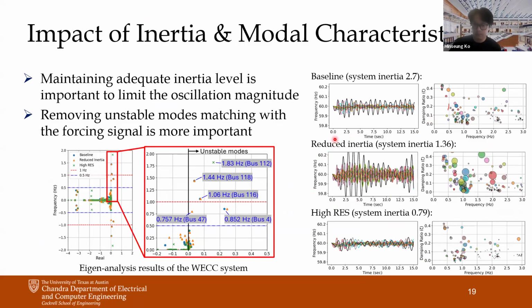So basically, I think the reason the high renewable energy sources case has a lower magnitude oscillation is not that the renewable energy sources control the oscillation. Basically, we are replacing the synchronous generator with renewable energy sources, and there are some modifications in the modal characteristics of the total power system, as shown in the left figure. Although it was not an intended change, the unstable modes that already existed in the conventional system were removed when we modified these conventional generators into renewable energy sources.